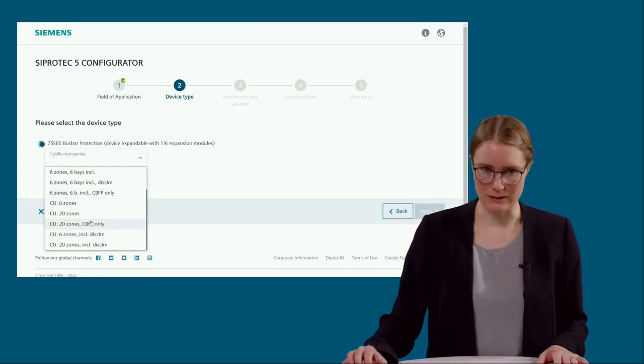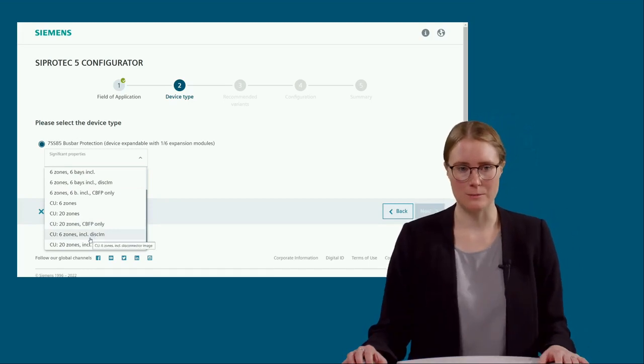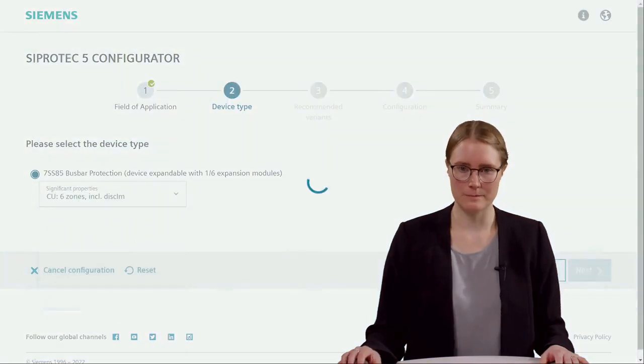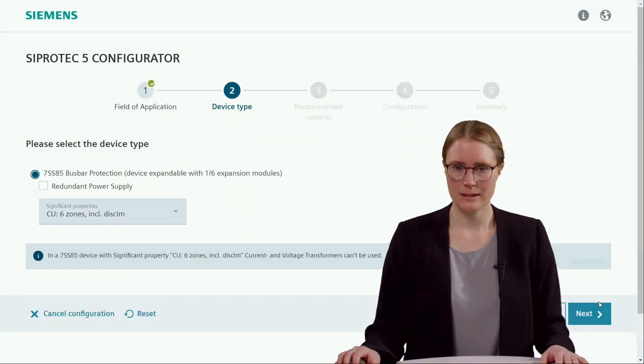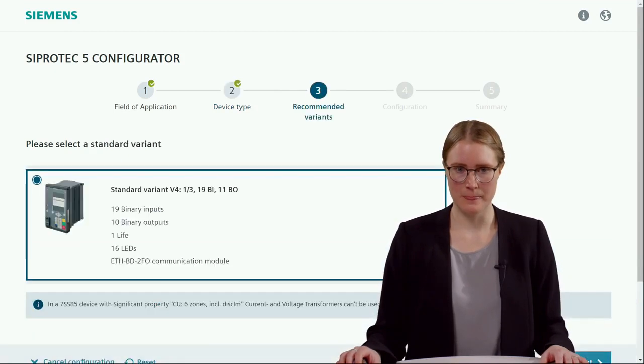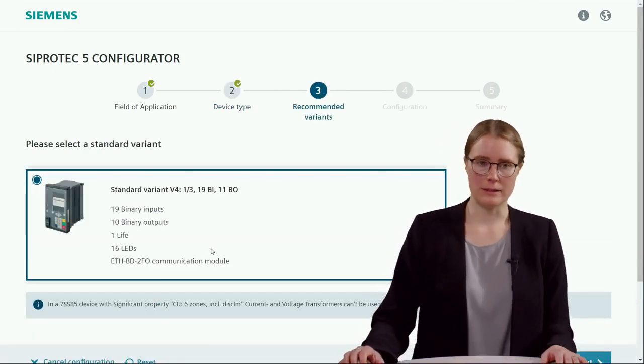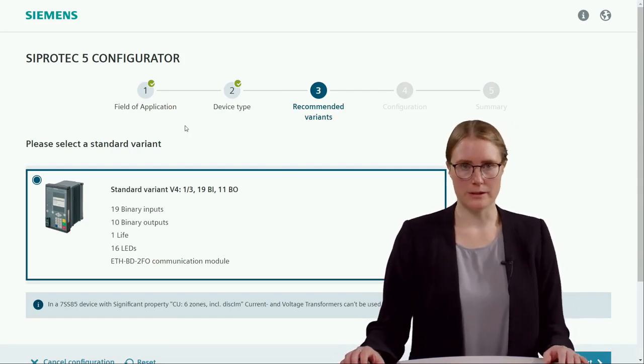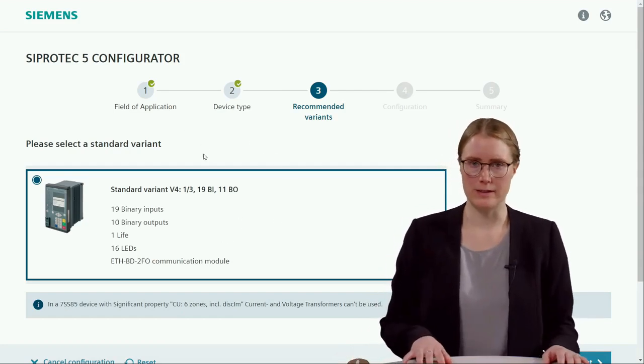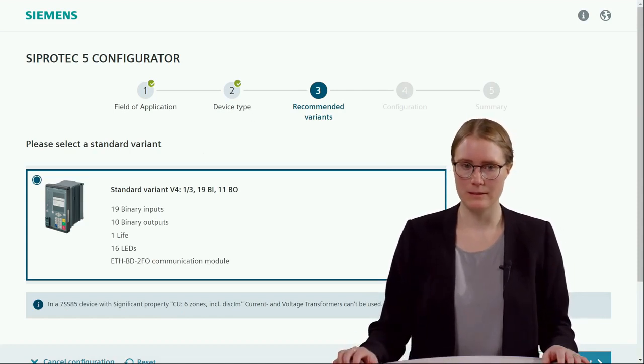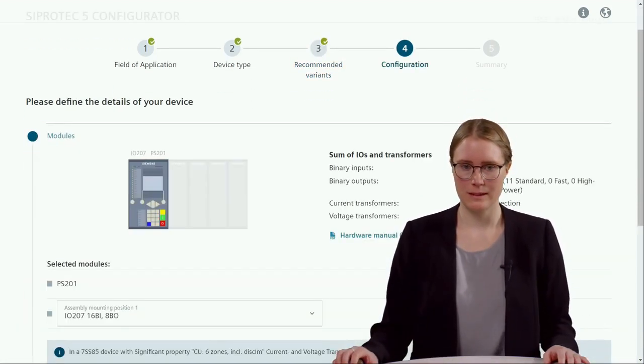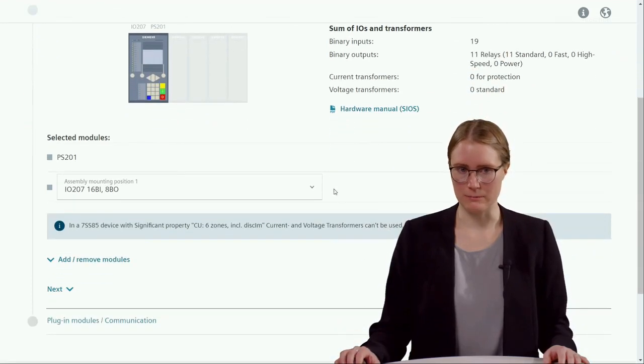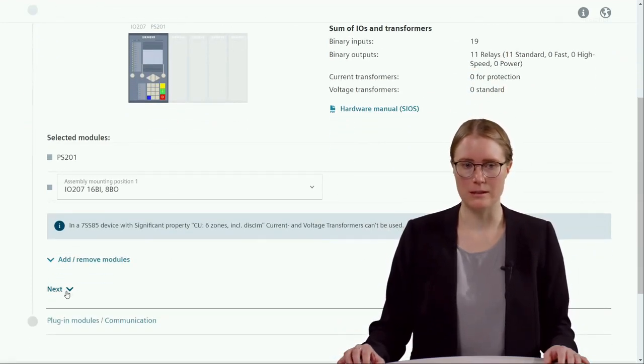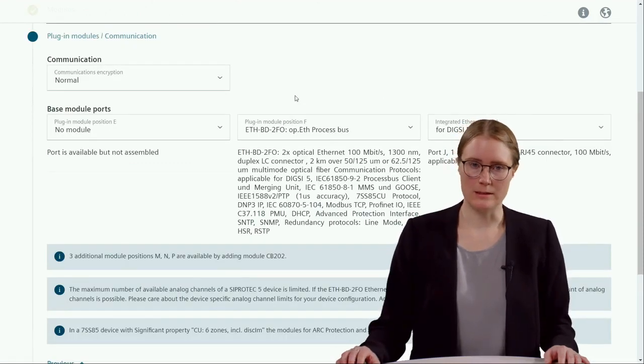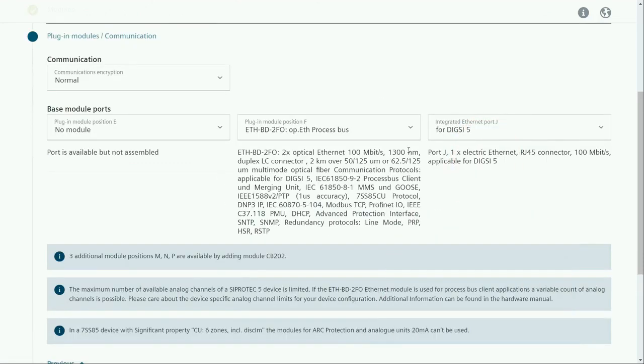And in our case, we are still interested in the disconnector image. So I go here with the 6 zone, including the disconnector image. Confirm this step. And here only the standard variant V4 is offered because this is the only interesting one for the 7SS85CU solution. Okay, no additional extension modules are needed. And here, once again, the BD module is already included.